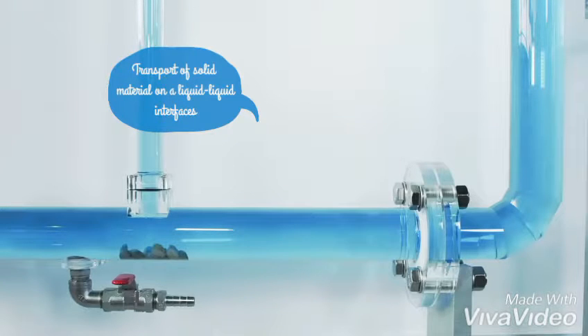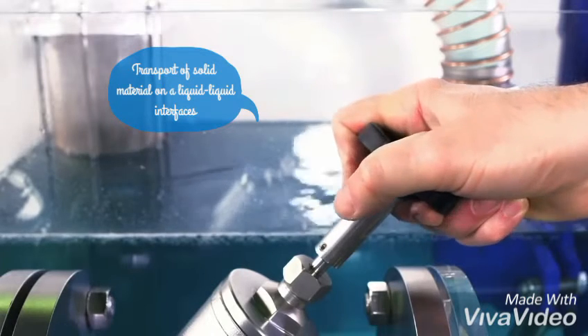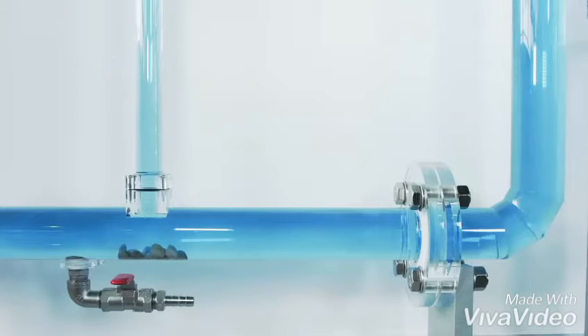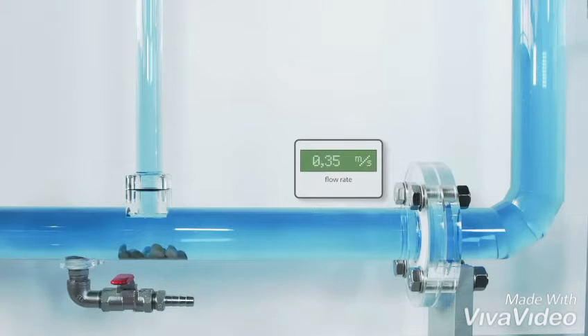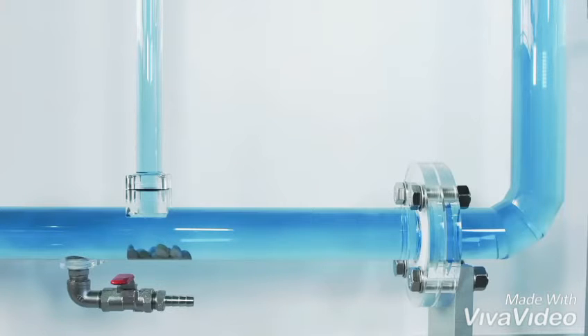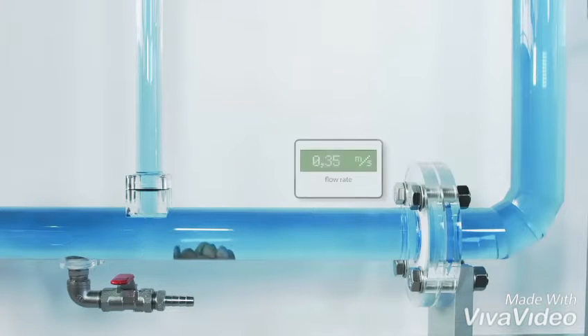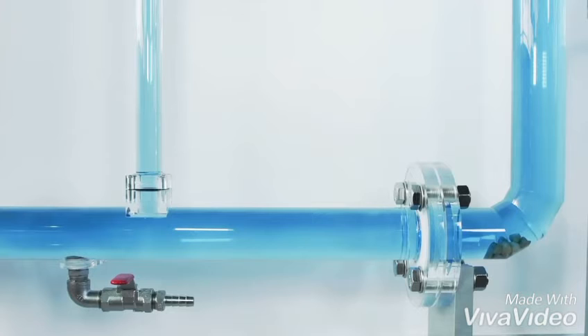This hydraulic model thus demonstrates the relationship between solid transport and minimum flow velocity in horizontal and vertical pipe sections. In waste-water pipes, solids deposits must be prevented. Examples are fibrous, sand, gravel, or metal particles.